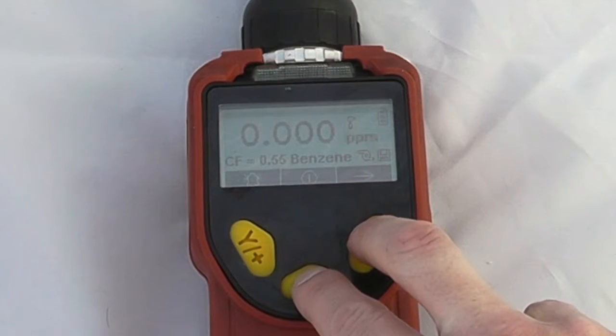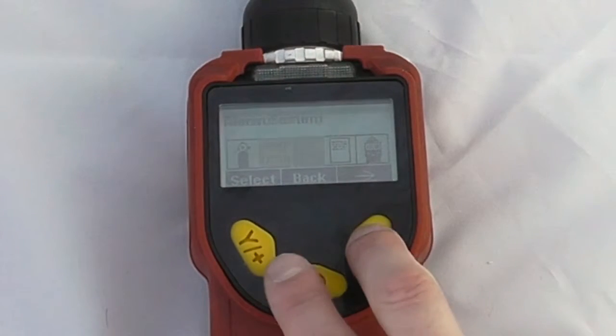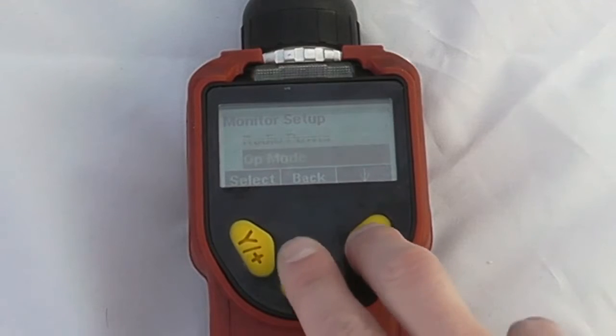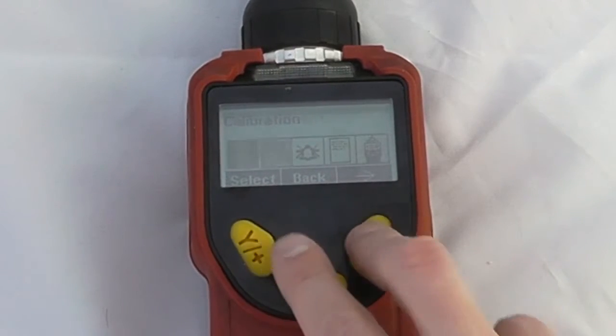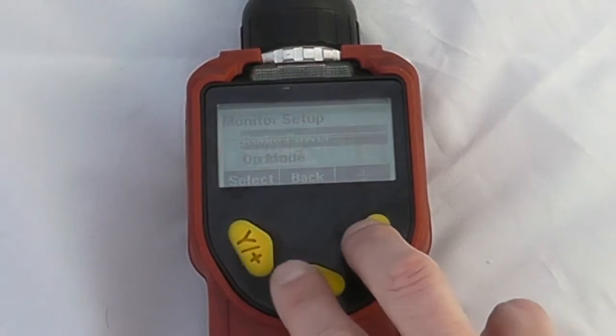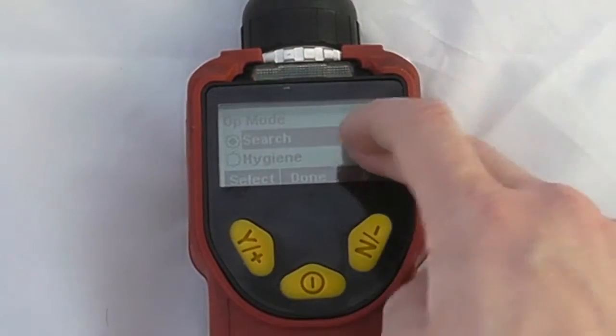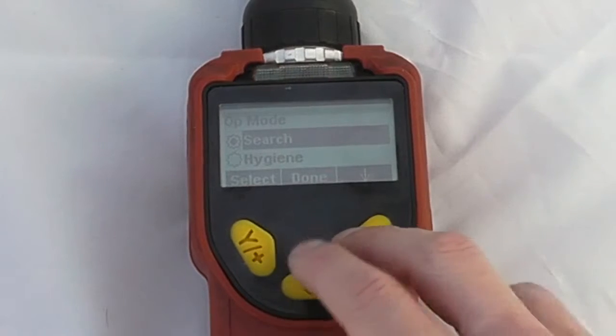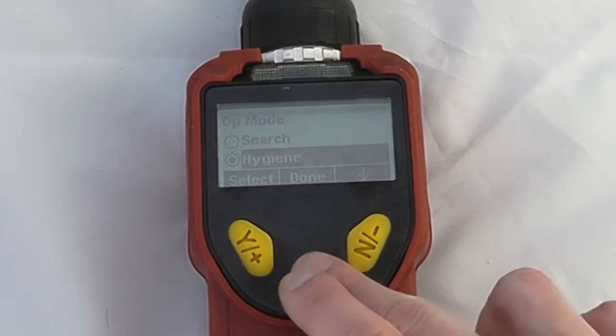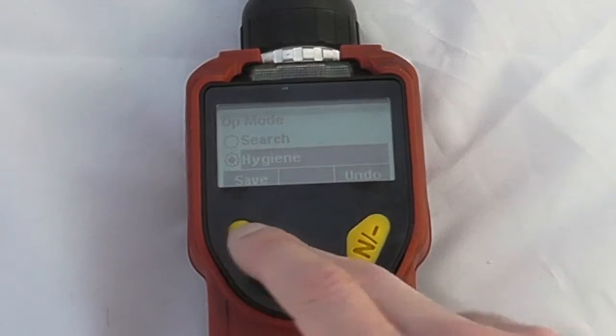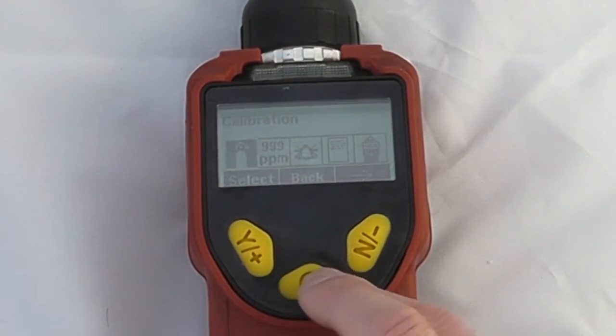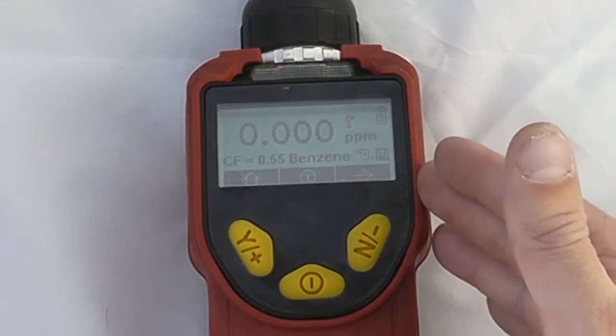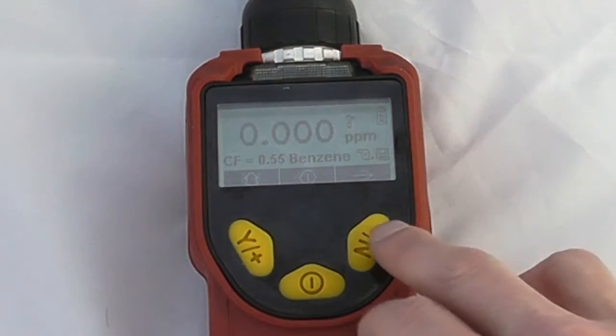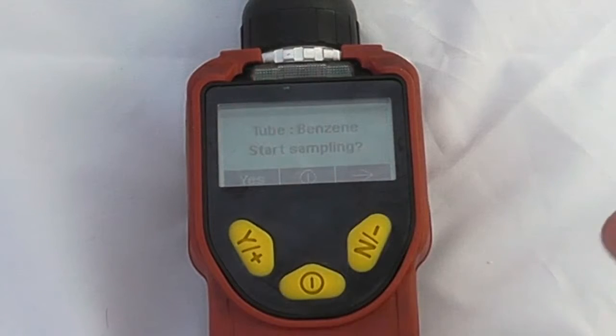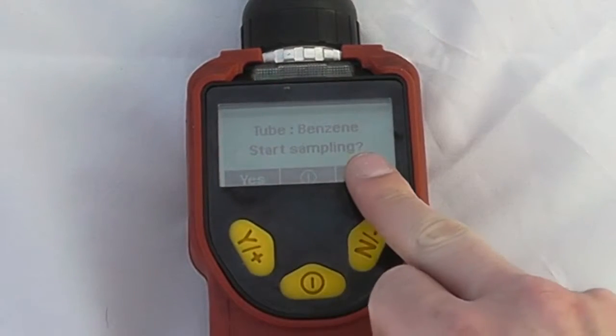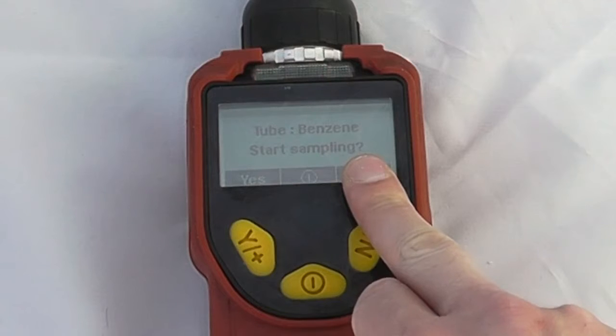If we now skip back into measurement mode, and we will change it from the monitor setup, the monitor operation mode. We are currently in search mode, but if we move it back into hygiene mode, we'll see that the instrument interface is in a slightly different way. So we'll now save that, go back to normal measurement mode. Now this means the instrument is now running from startup, so we can see we're establishing a TWA, but if you want to do a benzene measurement, we then push across. It is important to do a benzene sample if you want to do a benzene specific measurement.